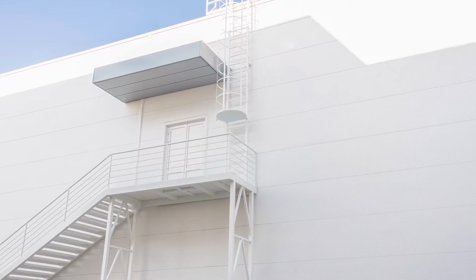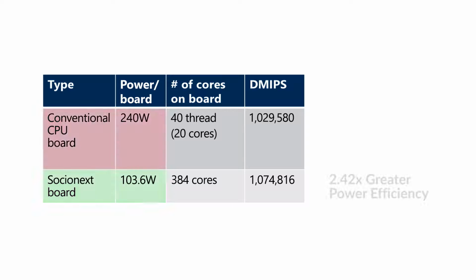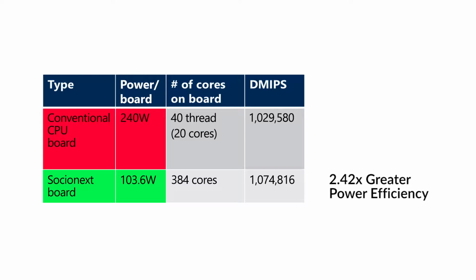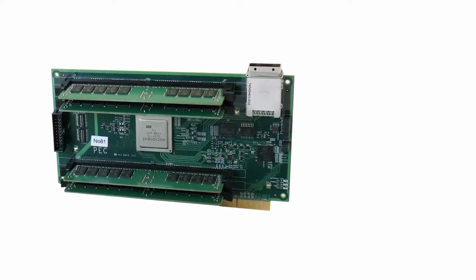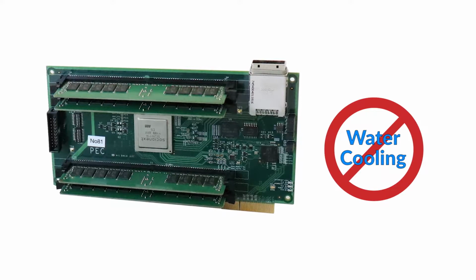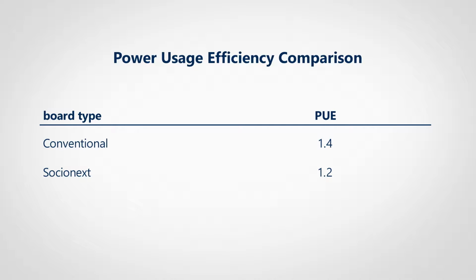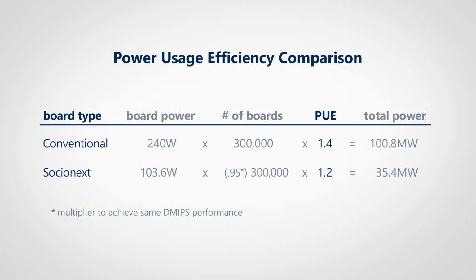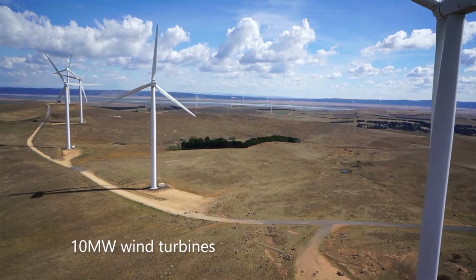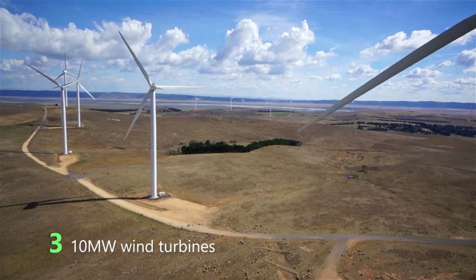At the data center level, the Socionext server solution has a power efficiency about 2.5 times higher than conventional-based systems. Additionally, the Socionext small core solution does not require advanced water cooling, so the power usage effectiveness is superior. When performing a side-by-side comparison of power efficiency, the conventional system produces the value of 1.4 PUE, whereas the low-power multi-core system using power-efficient ARM cores has a PUE of just 1.2. In a data center with 300,000 servers, switching from conventional systems to Socionext-based systems would reduce the number of 10 megawatt wind turbines required to power the data center from 10 to 3.